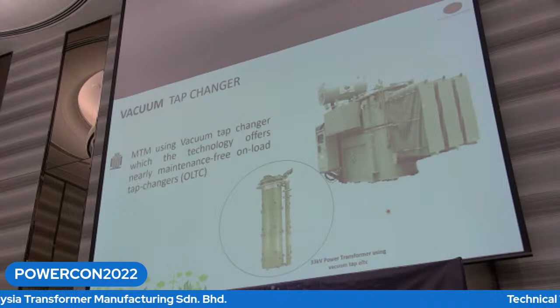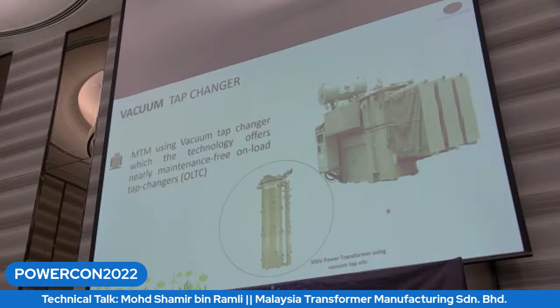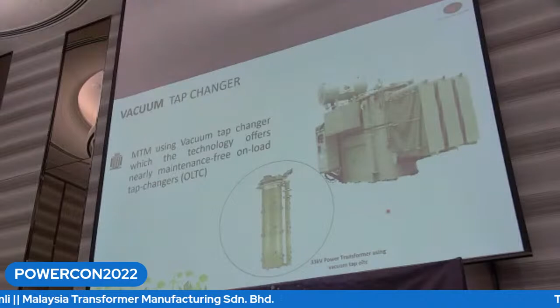But in the Malaysian condition we have to be worried about the moisture as well, because as you know, Malaysia has 80% high humidity. So yes, we don't have arcing inside the oil, but we still have moisture. Hence, from time to time, we need to monitor the condition of the oil.